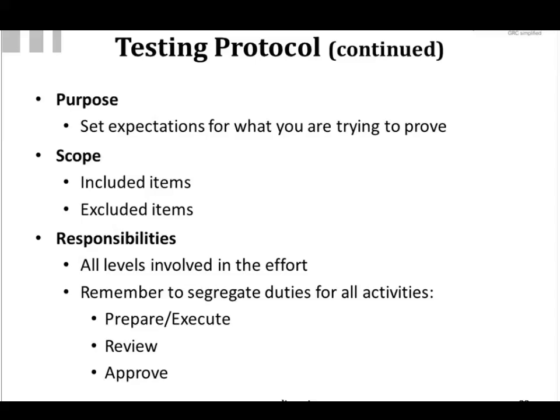Responsibility should be highlighted for every level involved in the effort. So again, you want to segregate duties. You'll have someone preparing the test scripts. You'll have someone executing them. You'll have another person reviewing and another person approving. Or you could have multiples of those.